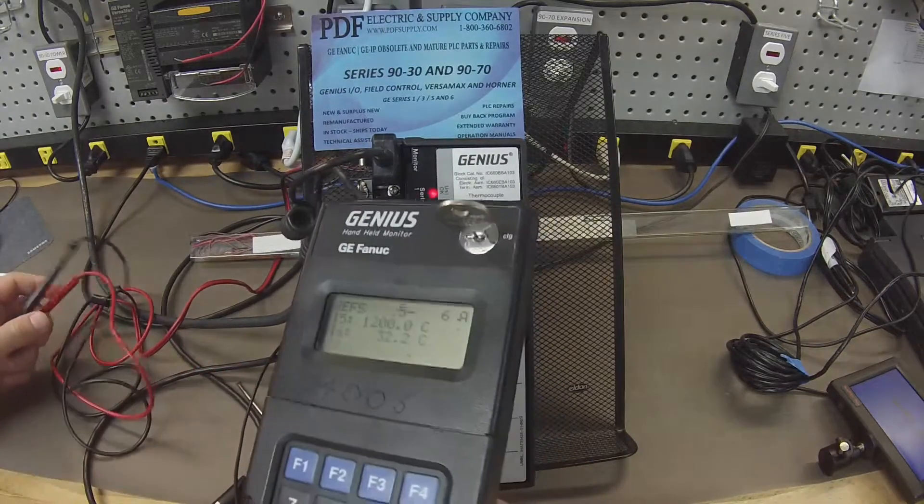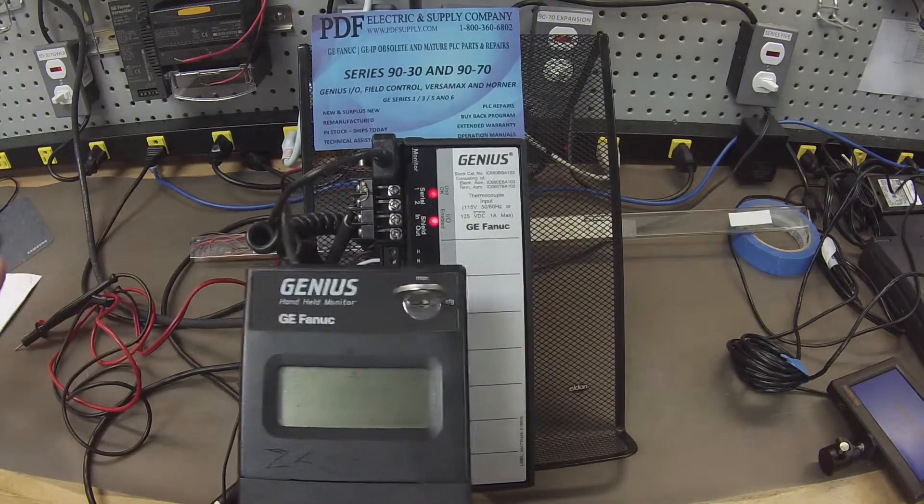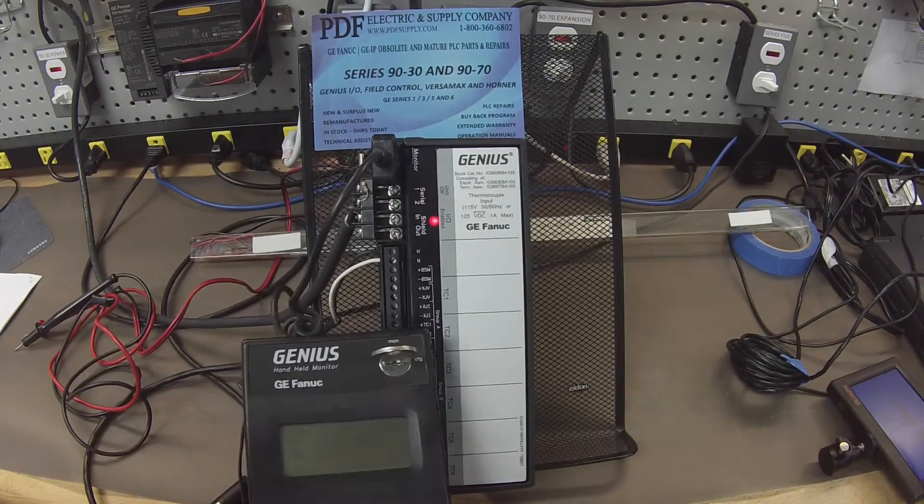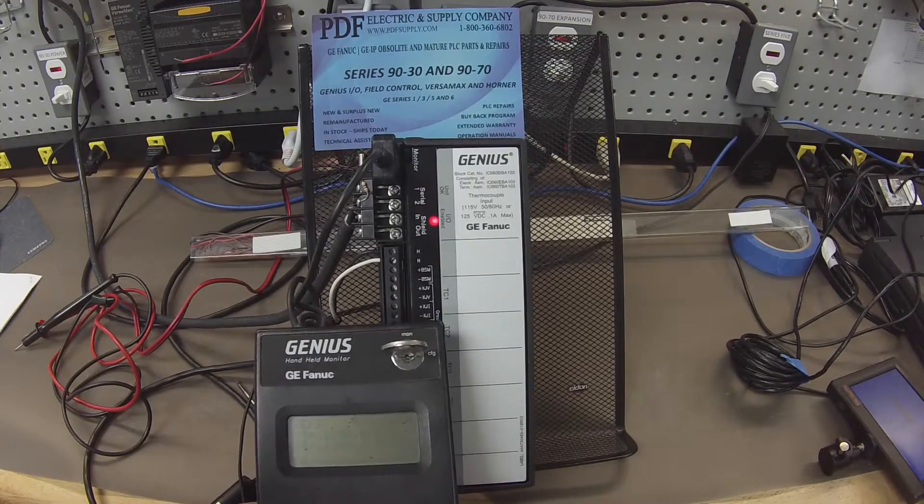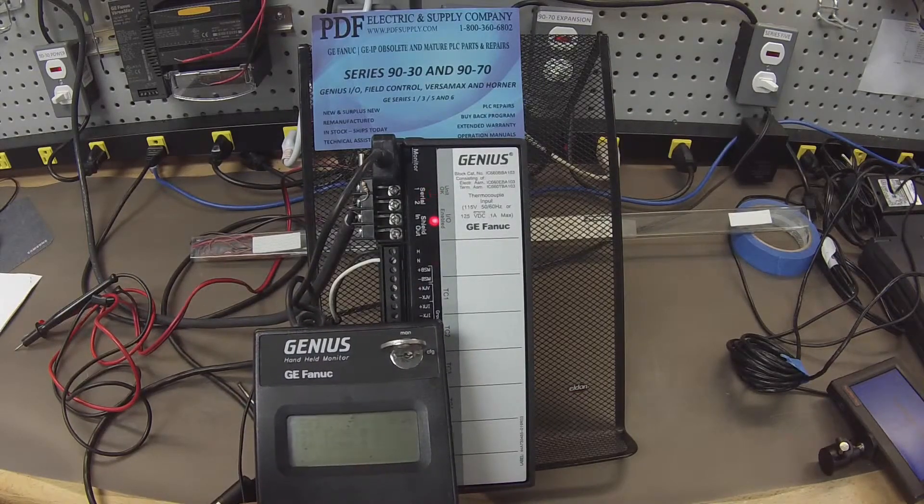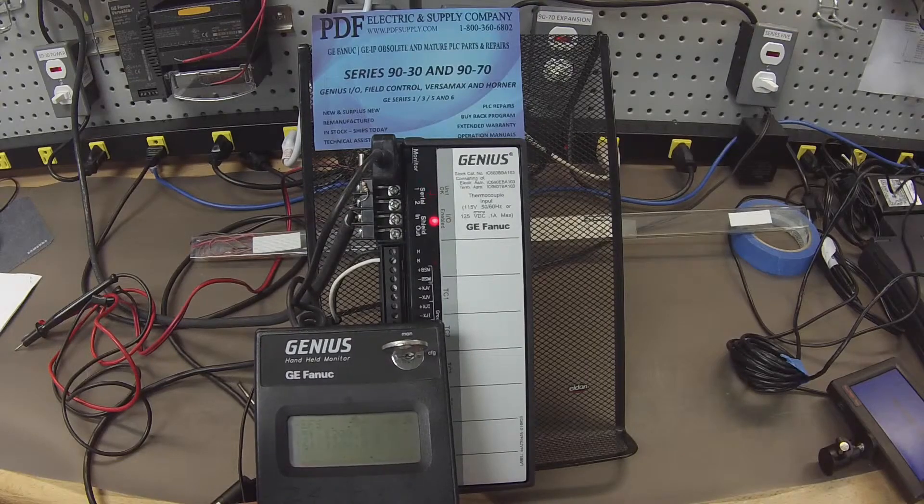So all my readings are pretty much the same, which is good to see. They're all within one degree, and that's good. If I held them on there long enough and tightly enough, I would likely get the exact same reading on every single channel, which is what you really want.